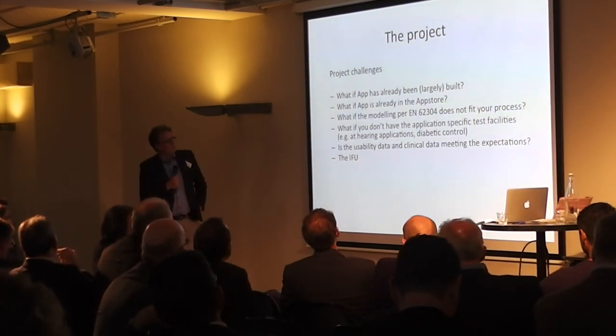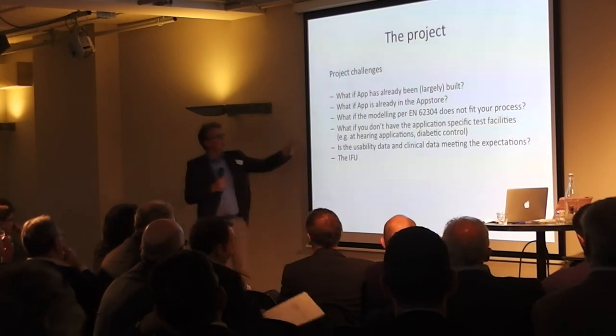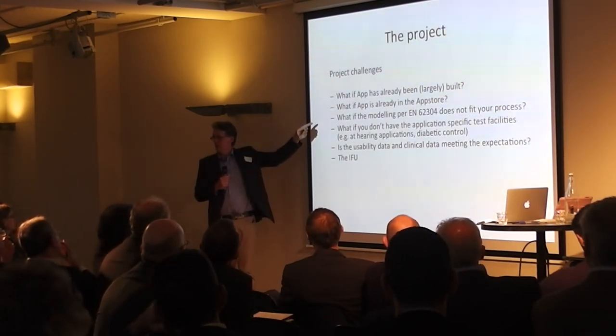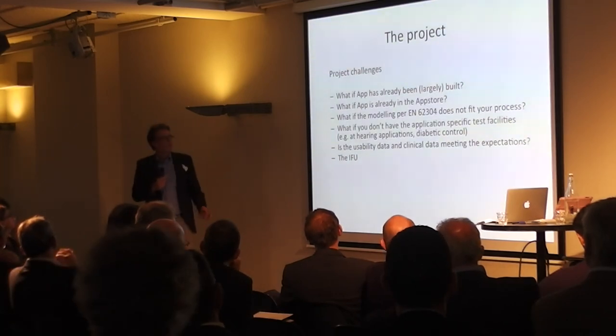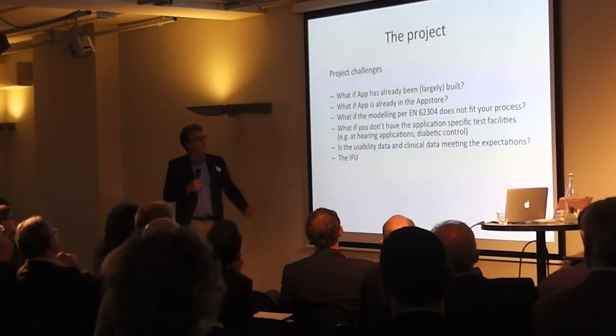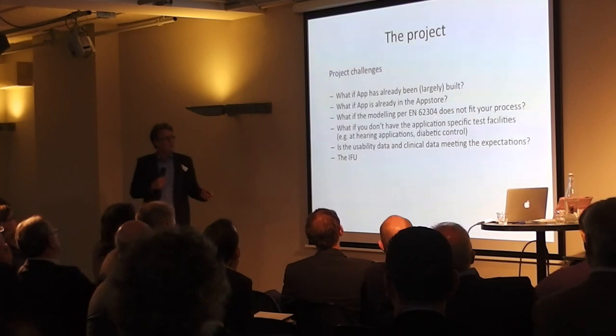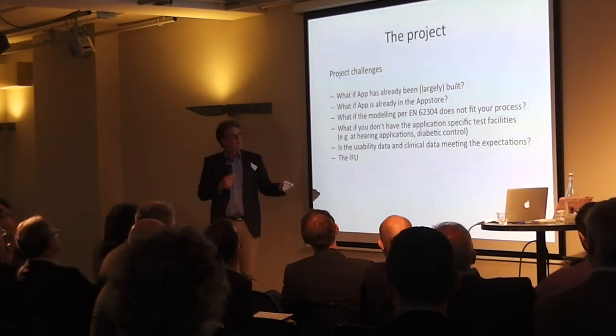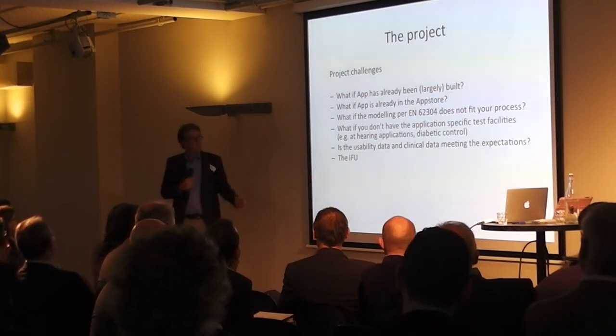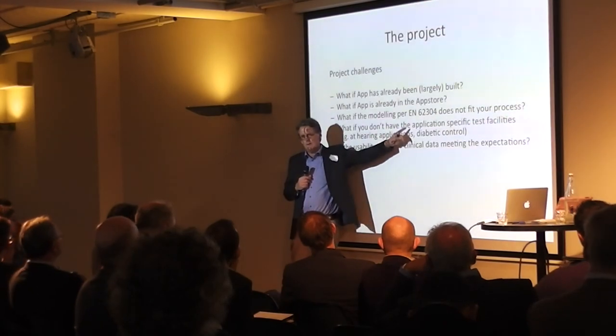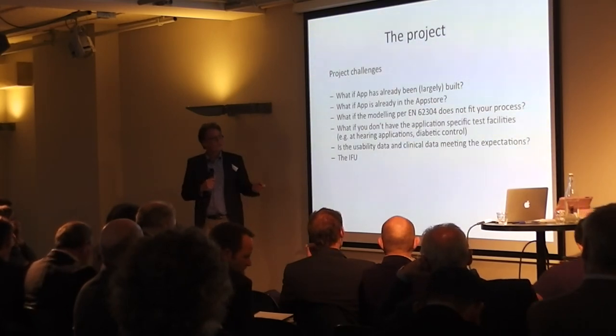In practice you will face a number of challenges. In agile development you may have already built your app, and all of a sudden realize: this is a medical application — what do we do now? It's running, it's available, and all of a sudden these medical device software requirements are very different. The rigid requirements of medical device software — a very structured way of software development — may not fit with your agile process. So you need to do some sort of gap assessment and argue why you still meet the intent of the standard. The standards are basically voluntary — you can come up with other means to comply, but it should still be closely aligned.